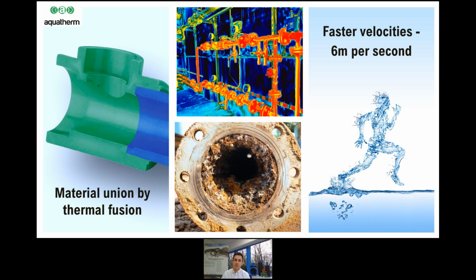When using metal pipes, velocity restrictions are necessary to avoid erosion, corrosion, water noise, and damage by water hammer. Due to the natural noise attenuation of Aquatherm pipe and the natural ability of the pipe to absorb the forces of water hammer, as well as the full bore diameter of the fittings, we can increase the velocities of the flow in Aquatherm pipe systems without compromising the ability of the pipe to prevent noise generation and water hammer. Aquatherm has published pressure loss and velocity tables to around 4.6 metres per second. However, Aquatherm has allowed engineers to design as high as 6.1 metres per second, depending on the system.